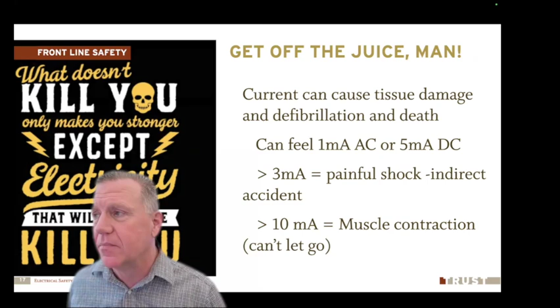I can feel it or feel pain at about 3 milliamps. At about 10 milliamps, I have muscle contraction so I can't let go of the conductor, and that can be really bad because the shock keeps going. At about 50 milliamps or above, it causes my heart to contract or fibrillate - ventricular fibrillation, causing my heart to twitch and lose its regular rhythm. At 100 milliamps or above, up to about 4 amps, it's almost always fatal if it gets in the right spot. Above 4 amps, heart paralysis and severe burns.